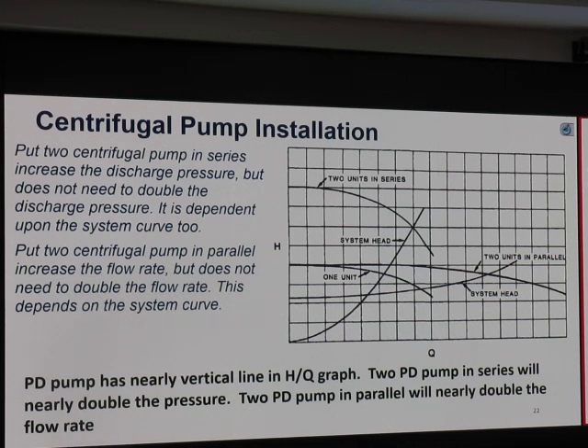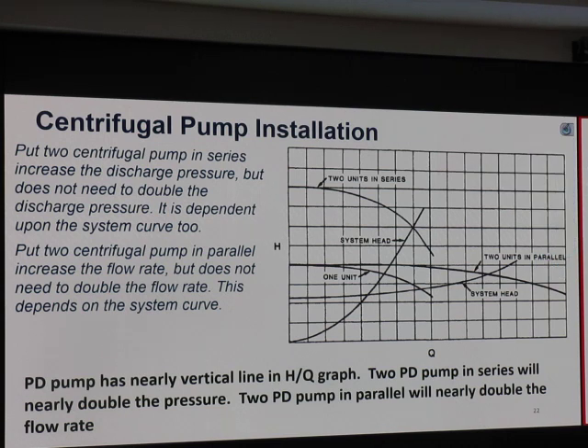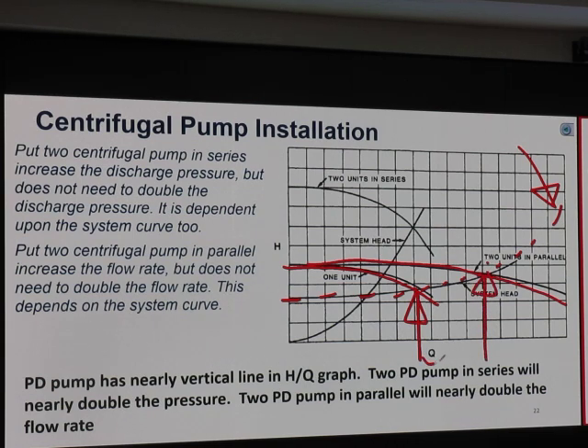Let's take a look at centrifugal pump. One pump, and two pumps. So when I have one pump, it looks like that. Two pumps in parallel, it looks like that. And this is my system curve. Do I have double in flow rate? No. The flow rate goes up, but it's not double. So it goes up from this point to that point. So this time is less than that, right? So when we put two pumps in parallel, the flow rate goes up, but it does not need to double the flow rate.